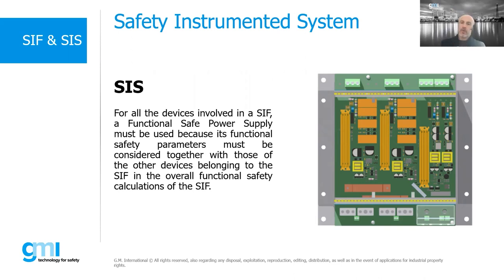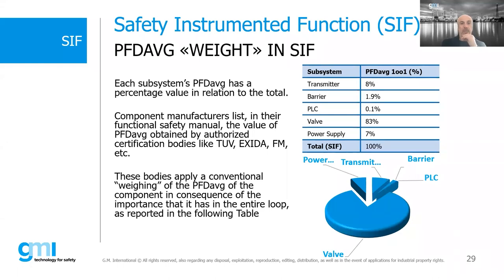We have highlighted this point. So also the IEC 61508 is very important. It is highlighting the importance of the safety power supply, the power supply that must be included in the loop calculation. So this is the first important concept. We see here how this power supply is taking part. It's a part of the SIF, so each subsystem has a percentage. Of course, the valve in the loop is the most important part, and because it's the mechanical part, it must be tested probably with a higher frequency than the electronic components. But also barriers, transmitters or others have to be tested, and the power supply too. So there is a special, let's say, weight of also the power supply in the loop.